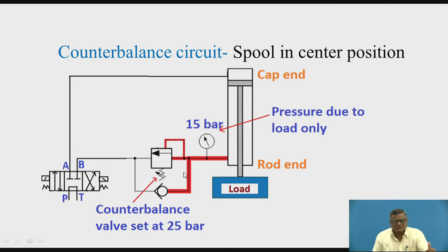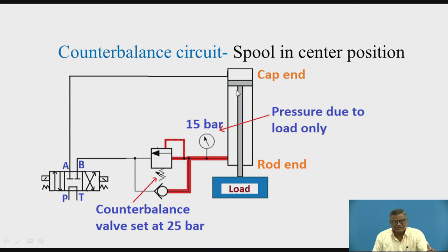Now, 15 bar is the only pressure — it is due to the load attached here, and the piston rod and piston weight. These are the contributing factors to that pressure. The oil has come up to the counterbalance valve and remained there. No further flow through the counterbalance valve is there, and the load is retained there only.